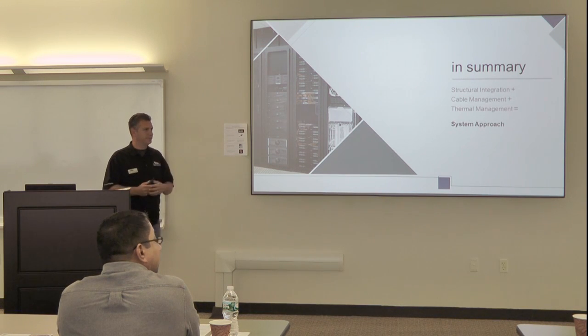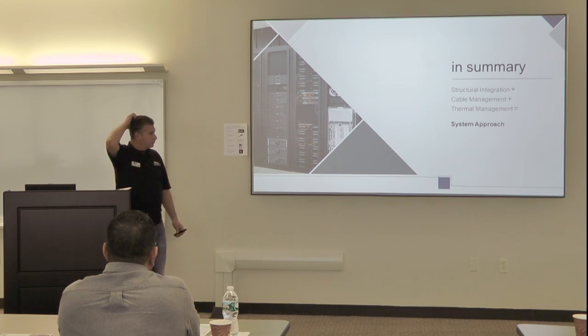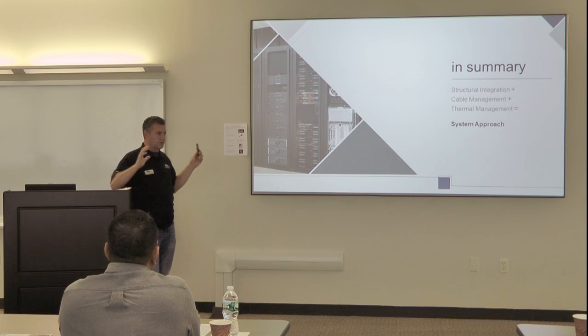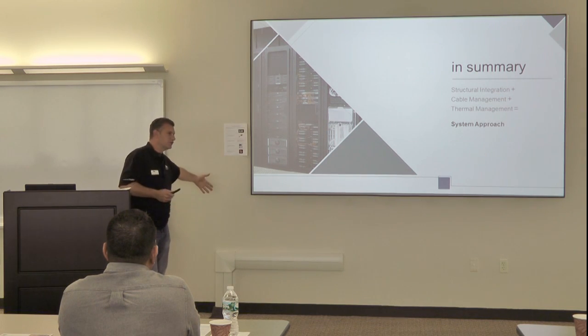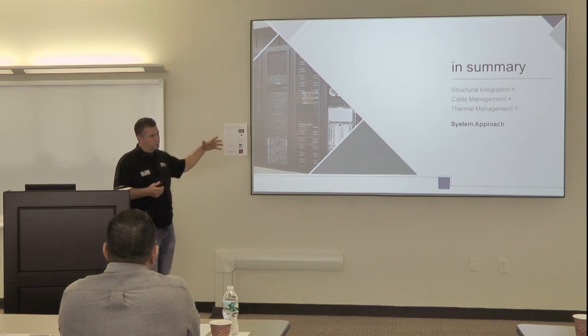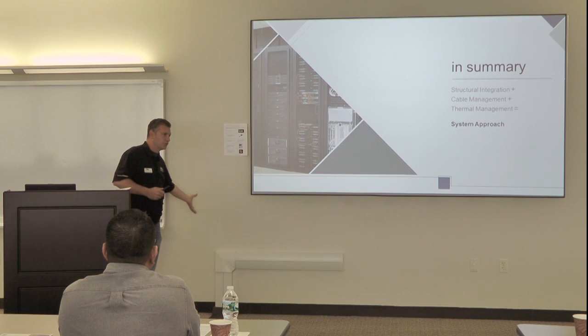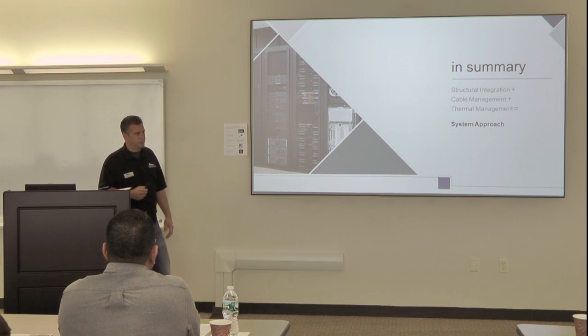Any other questions? What about just managing heat in credenzas? One of the things you want to do is not have the heat come out, and a lot of times the credenza is up against the wall. So depending on the credenzas you're using, some of them are built to have cooling in them. Other ones, you could look for a smaller fan that can go on the side to blow the heat out the side. The best way to do it is bring cool air in through the front and out the back, but a lot of times it's up against the wall, and you don't want to bring it up and through. So usually what you'll do is some kind of cooling on the side, because in the back you just don't have the room for it.